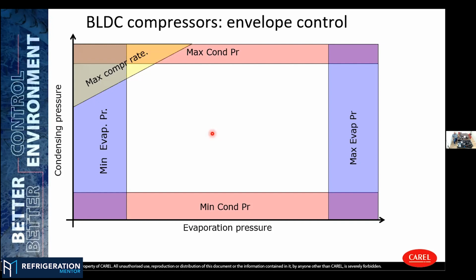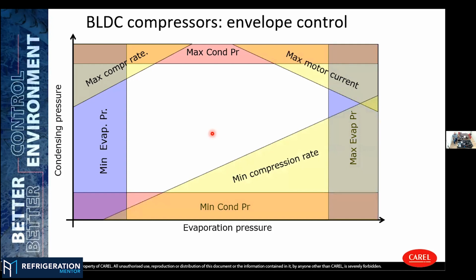We will add, for example, the maximum compression ratio. When you have a very high delta P between the evaporation and discharge lines, we also have a limitation in terms of maximum current. The motor is rated for some current, so you cannot overcome this threshold. And also, as we discussed, mainly for the oil lubrication process inside the compressor, we need to maintain a minimum compression ratio. So a minimum pressure differential between suction and discharge to make enough pressure for the oil to go from the bottom of the compressor to the compressor chamber. So this is the limitation.